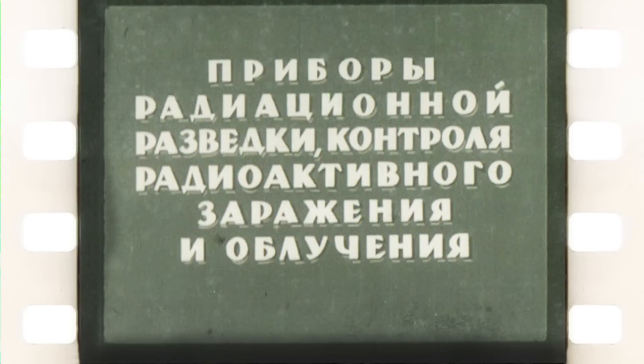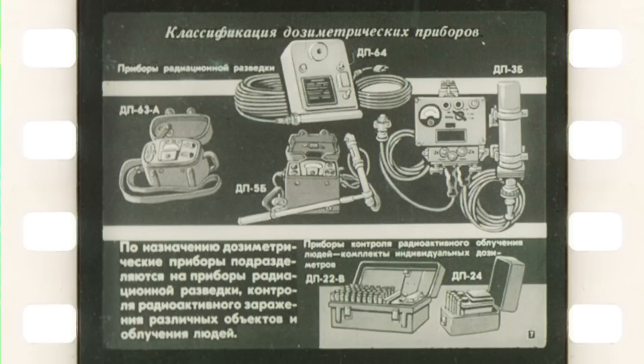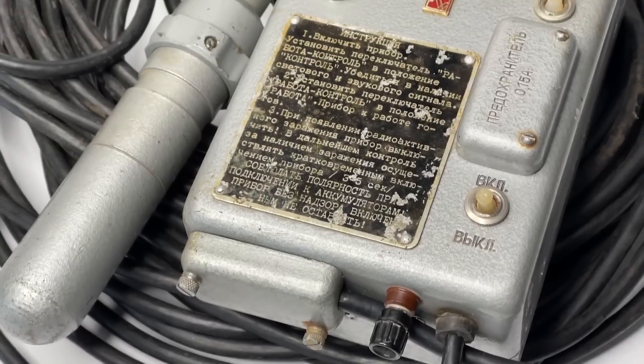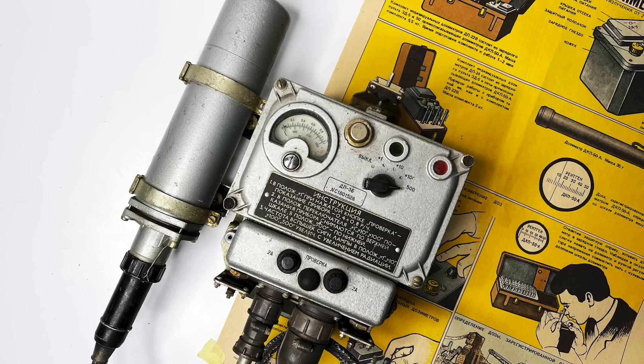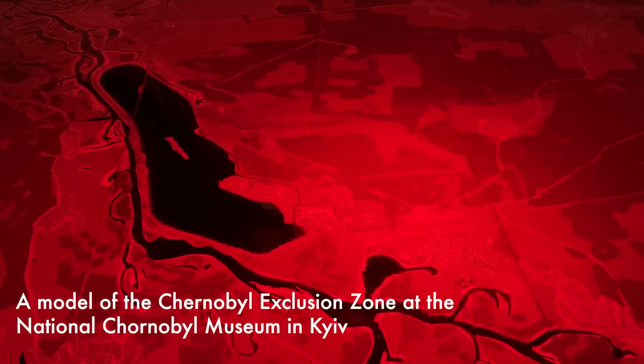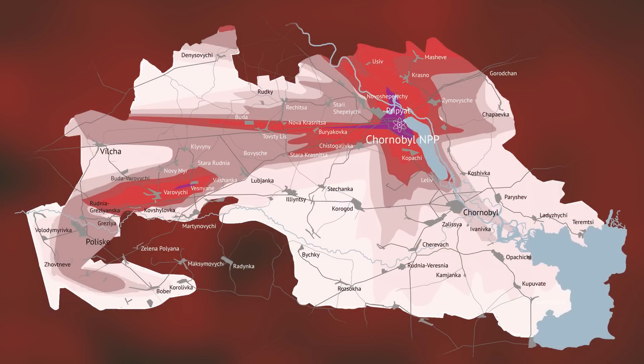Before we take a detailed look at it, it's quite important to give you an insight into the situation with these kinds of devices back in the day. During all their history, Soviets were sure that any problem with radiation could happen only in the case of an enemy nuclear attack. The majority of devices produced before 1986 were designed for quite specific effects and types of contamination, and moreover they were analog, which gave severe limitations. It appeared that was not enough for the new challenge. The Chernobyl accident was very different from a nuclear attack — the wind lift of radioactive dust created a patchwork-like contamination formed by a variety of nuclides, turning a giant area into a true terra incognita where everything looked usual but no longer worked in a usual way. Although existing equipment was widely used, it became clear that something new was needed.